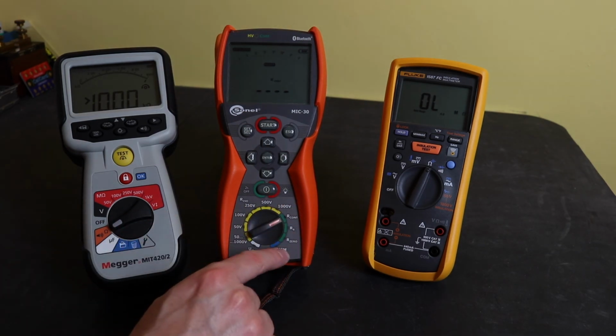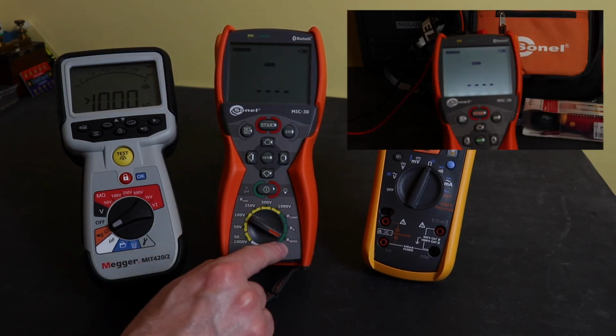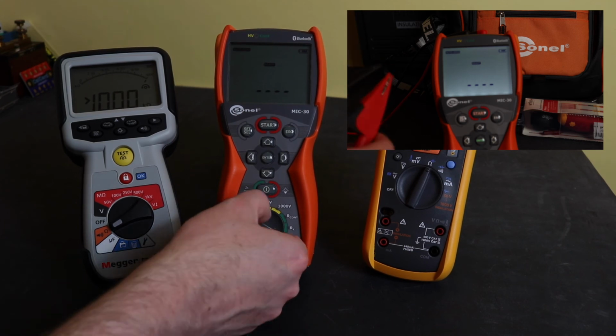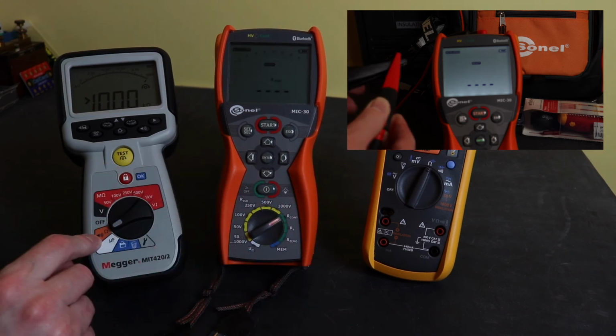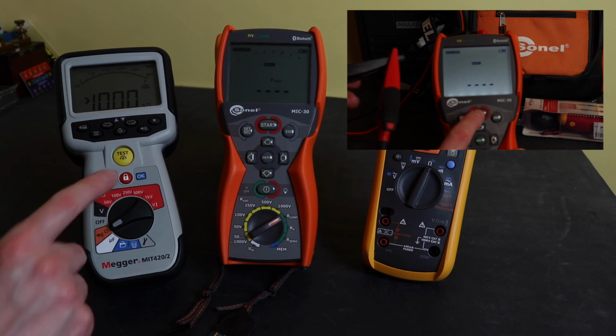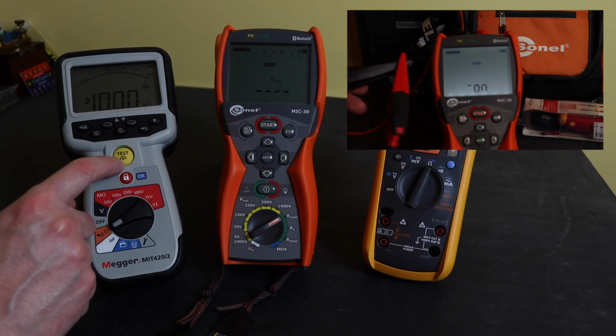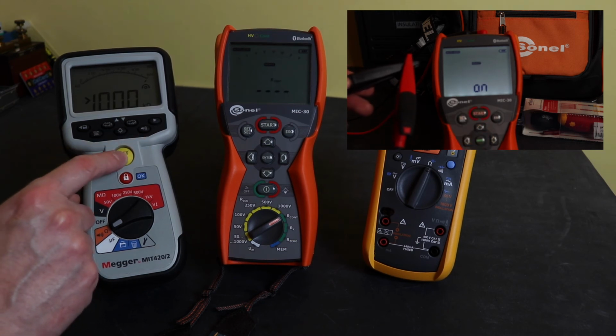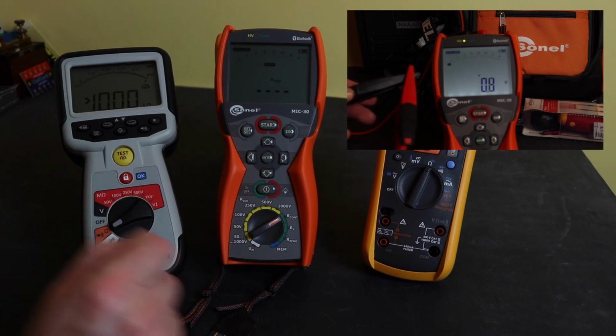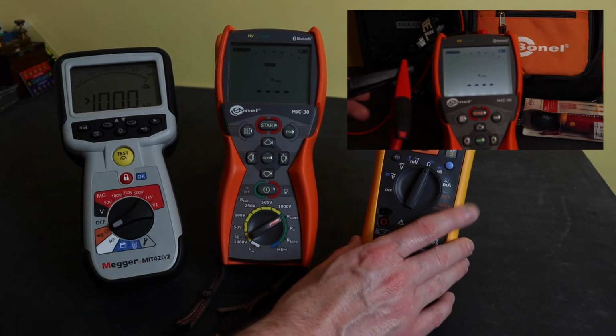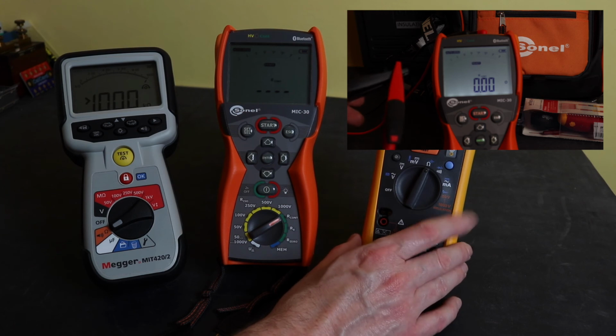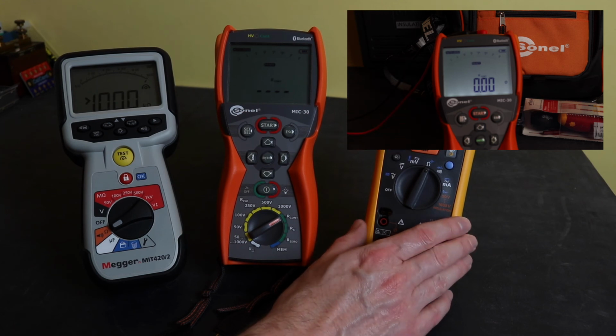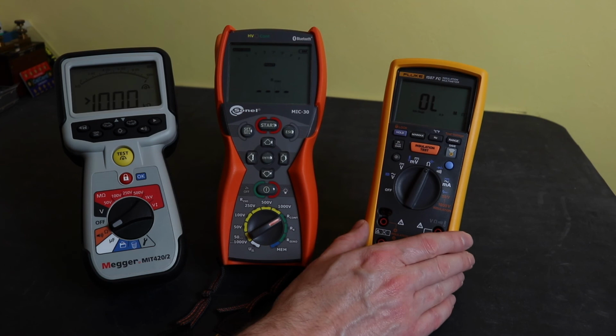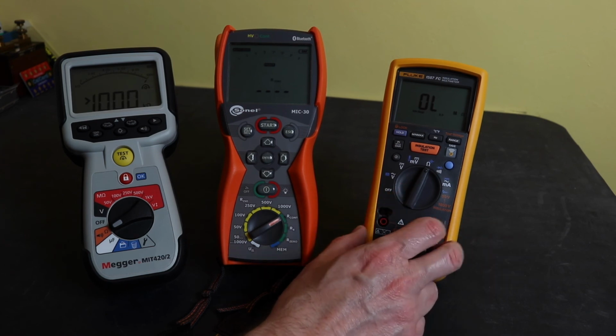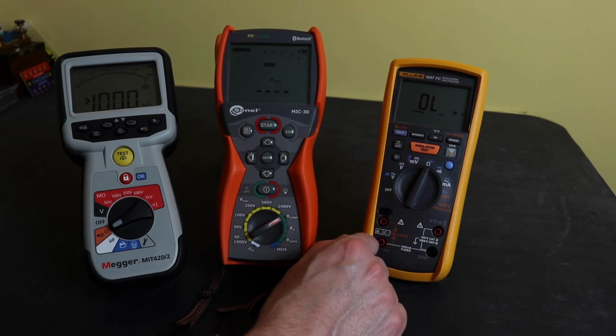As I said, lead zeroing on this is off of its own special function on the rotary switch for the Sonel. For the Megger, you do it on the same range with the zeroing button here, which doubles up as the test button for an insulation test. Interestingly enough, for the Fluke here, you have no lead zeroing function built into the instrument, which is quite surprising because it's a relatively standard function for a multimeter.